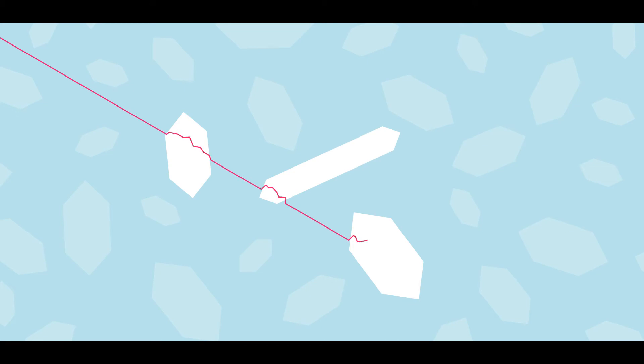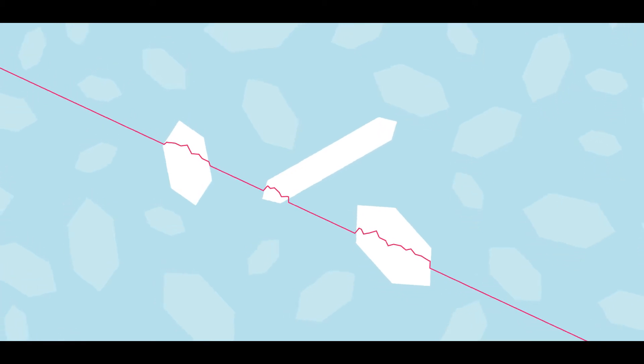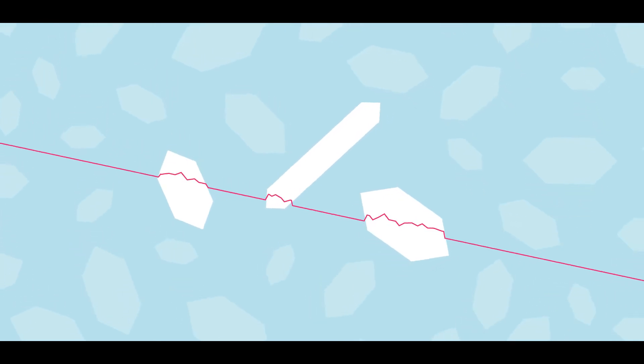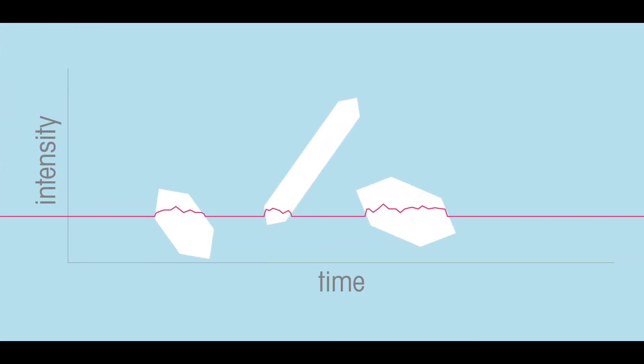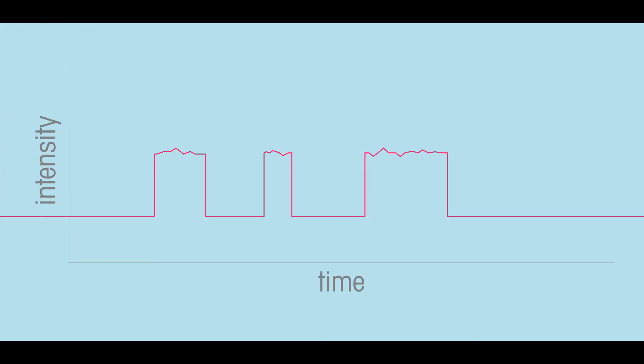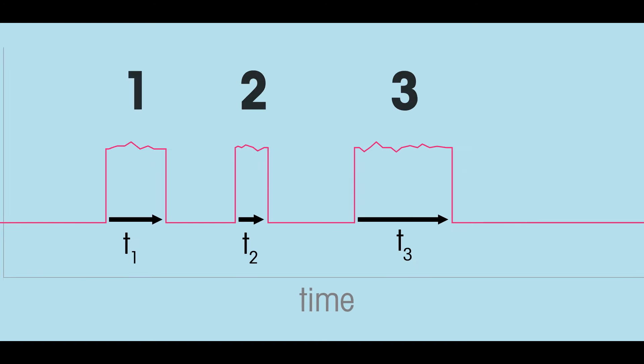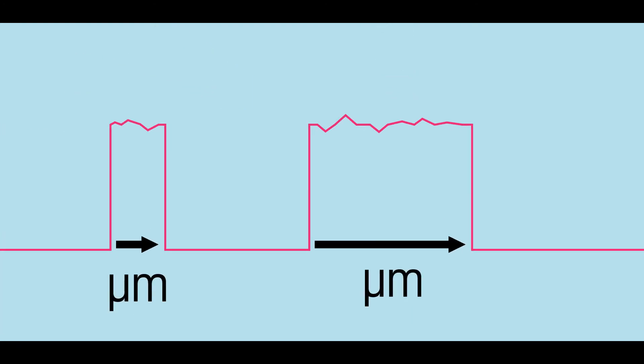As the focused beam scans across the particle system, individual particles or particle structures backscatter the laser light to the detector. These distinct pulses of backscattered light are detected and counted, and the duration of each pulse is multiplied by the scan speed to calculate the distance across each particle.